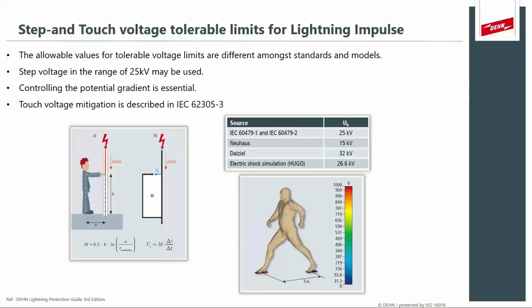In the beginning of this webinar, we spoke about the calculation for a 70 kilogram and a 50 kilogram person using IEEE Standard 80. That's for power frequency. As I mentioned, when we make the tripping time, or the fault clearing time, of circuit breakers faster and faster, the limit actually increases. Based on a lot of different sources and models, this is what some people over the world have come up with. There's an IEC standard that we reference a lot throughout this webinar as well. It talks about 25 kilovolts, and then other different body models. So for the purpose of this webinar, we will work on the 25 kilovolt limit, as this is one of the most common ones that I've come across in industry. We then have to control and ensure that there are no step potentials exceeding 25 kilovolts on the gradient. Now for touch voltage, it's also a little bit different.